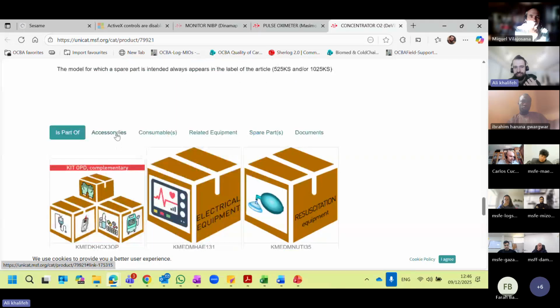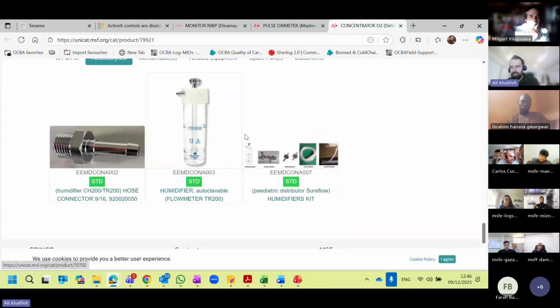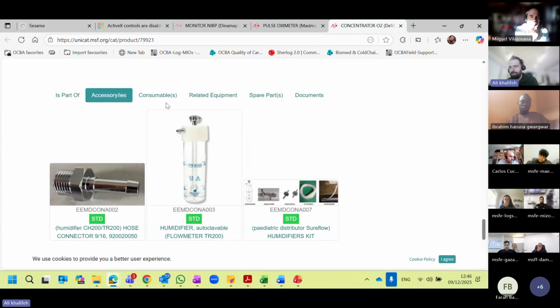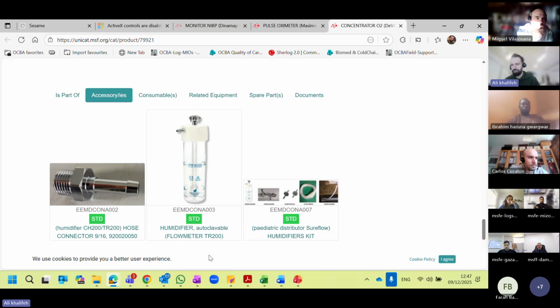What's important for us is the accessories section. As we said at the beginning of the training, accessories should be requested by the medical team. But since we are logistics and we are in the field, as biomed, for example, I know in our project that the flow meter TR200 breaks a lot for many reasons: misuse, mis-sterilization, and so on. So it was a good time to check with the medical team if they placed the order for this flow meter, and also a good time to share with the medical team and the sterilization department that they need to be more careful, since we had high consumption of this flow meter last year.